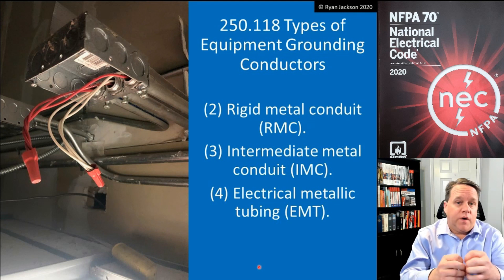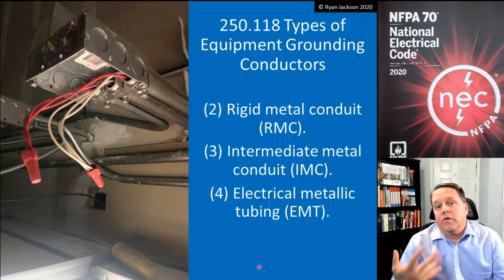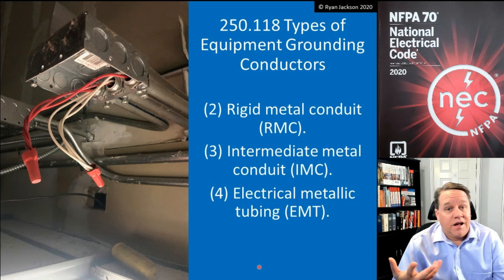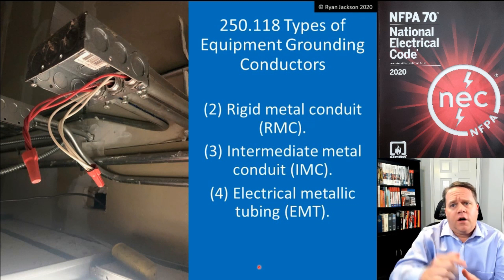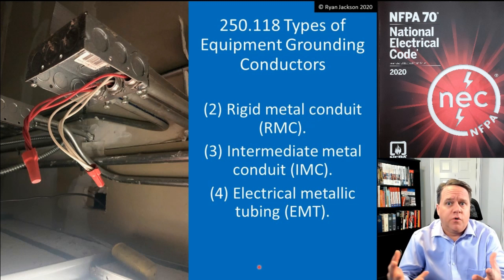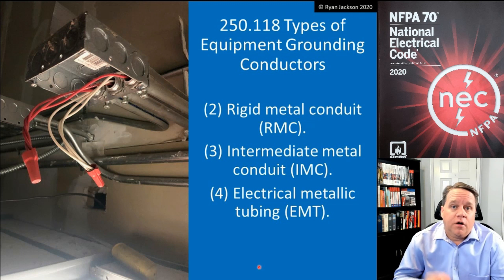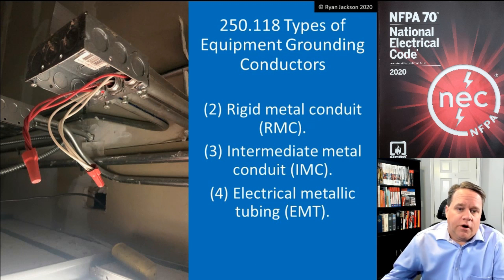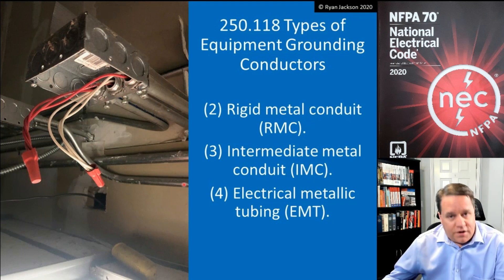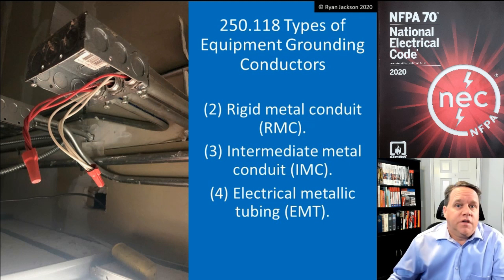As the galvanic corrosion occurred, that EMT disintegrated away to nothing. There was a ground fault in a restaurant called the Deli at the MGM Grand. The fault current went back to its source, ran into the corroded conduit, energized the conduit, and ended up lighting the building on fire. About a hundred people died and almost 800 were hospitalized due to smoke inhalation.